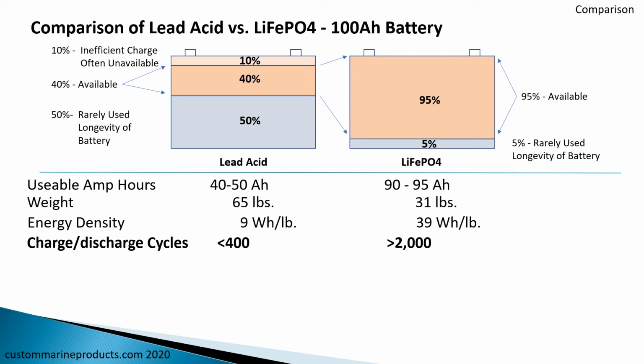The number of charge cycles we've talked about, typically on a lead acid, a charge cycle being drawn down to 80% of its capacity and then recharged. Or in the lithium iron phosphate, the 2000 number is drawing down 90 to 95%. So we have literally 10 times the charge cycles. And I say 10 times because if we drew down the lead acid 50%, we'd get about 400 charge cycles. If we drew down the lithium iron phosphate just 50%, we would have literally 4,000 charge cycles. So it's literally 10 times the length.